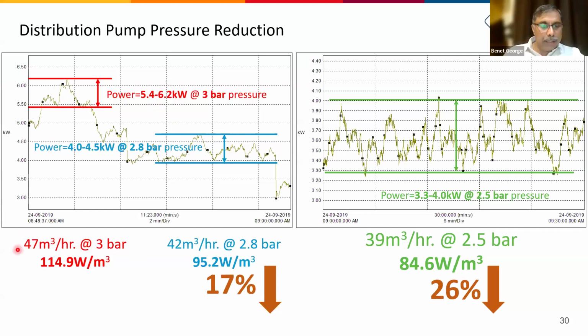Then in the energy consumption, you can see 47 meter cube per hour was supplied, and it was coming to around 114.9 watt per meter cube. In the second case, when you reduce by 0.2 bar, it came down to 95.2 watt per meter cube. So that is a 17% reduction. Then it was further reduced to 2.5 bar, and the power is 84.6 watt per meter cube. These are actually recorded values, and a digital pressure gauge was available.